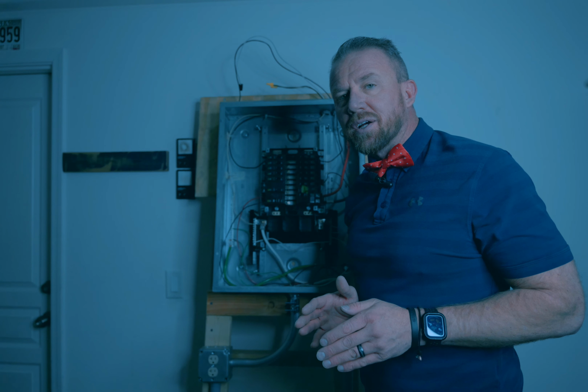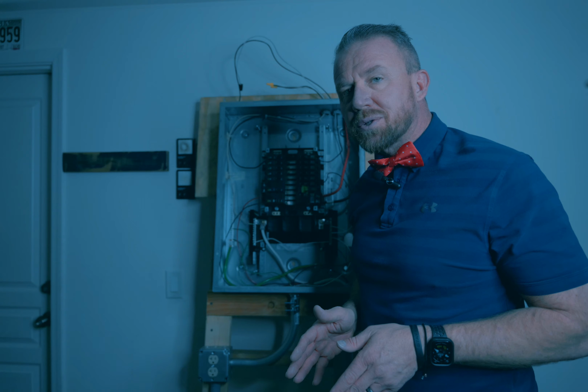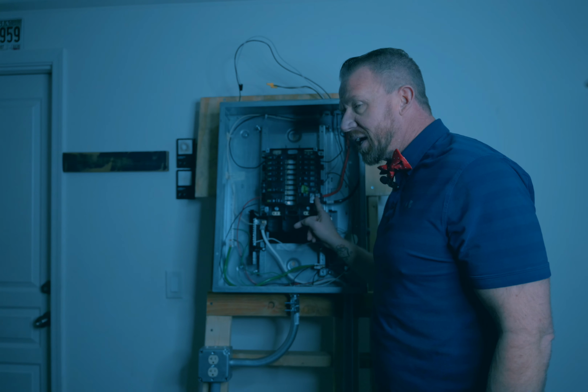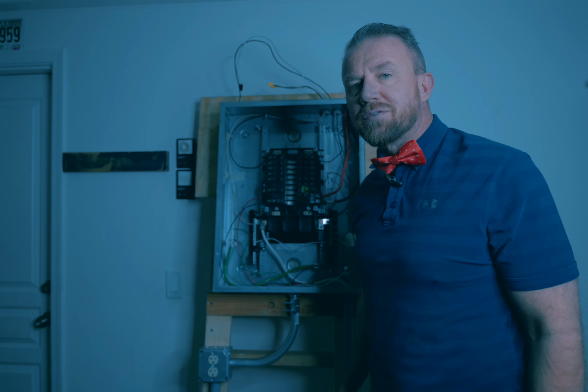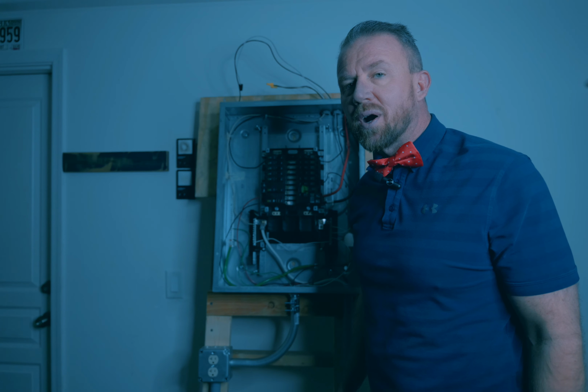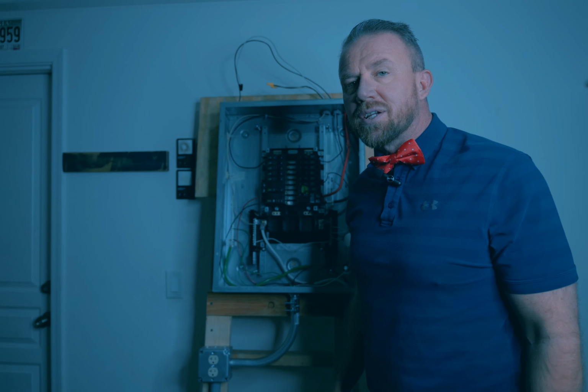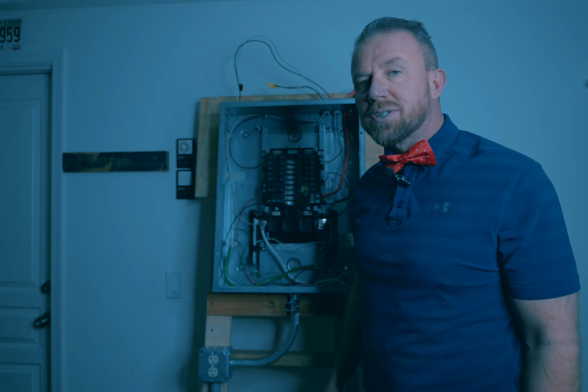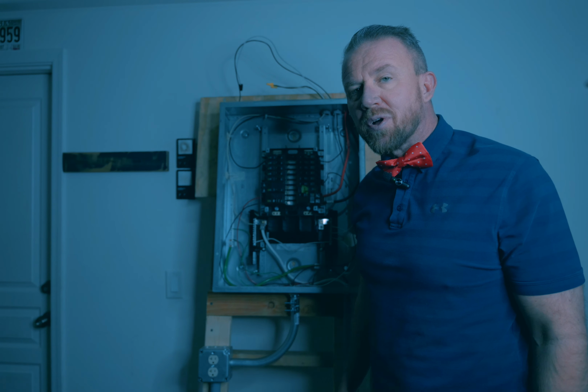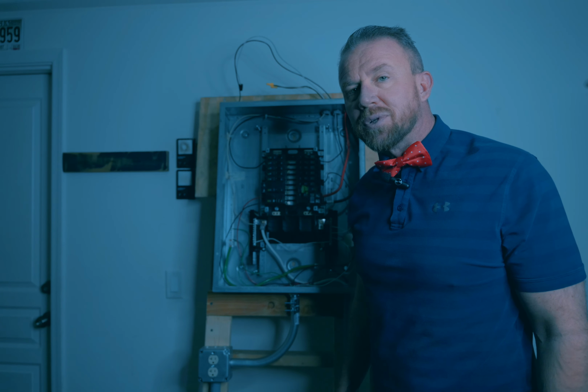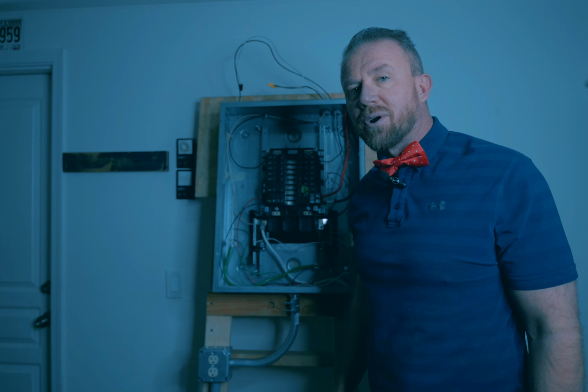If it's a double pole circuit breaker, meaning the wider ones with 2 inputs, you'll have to remove both black wires. It's a good idea to mark one with masking tape as top, or mark both, one top one bottom, for easy identification later.